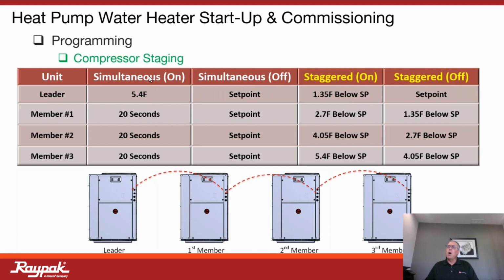So in the simultaneous mode for domestic water production, if I drop 5.4 degrees from my stored water temperature, the leader is going to suggest, boom, great. We have a demand. Let's call for heat. The unit is going to turn on. Well, there is a default adjustable parameter, but the default is 20 seconds. So in the simultaneous mode, after 20 seconds, the next unit will turn on. And then after 20 seconds, the next unit will turn on, and so on. So it's basically a bang, bang control. So all 4 heat pumps are going to stage on within a minute so that we can try and satisfy set point. As we achieve set point, boom, all units will turn off simultaneously.